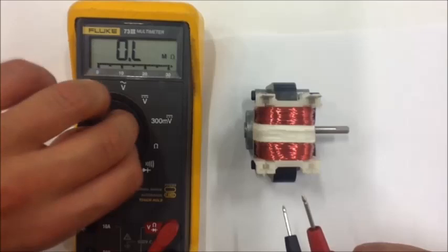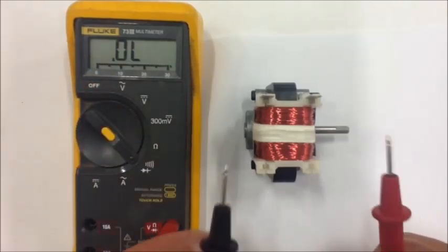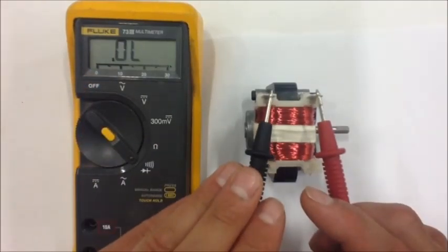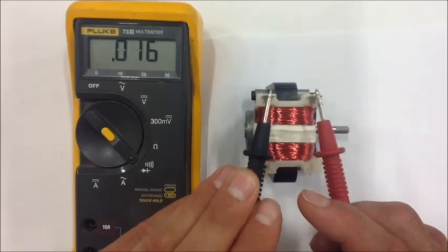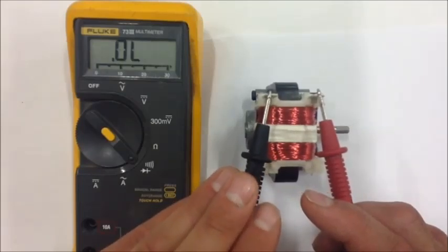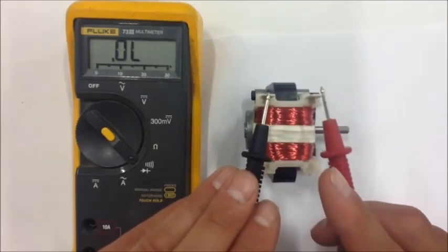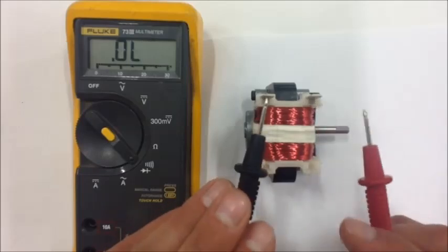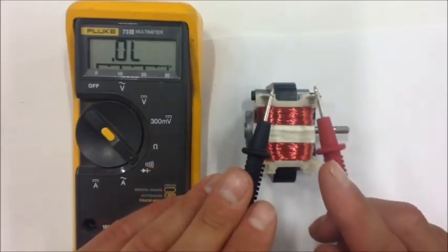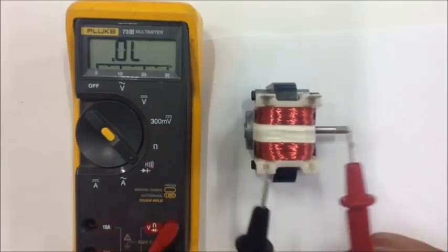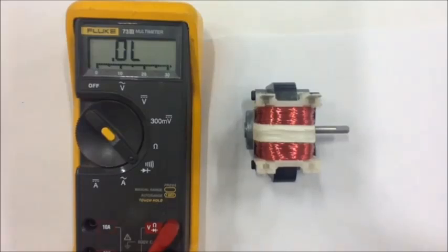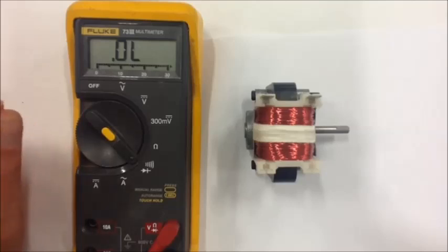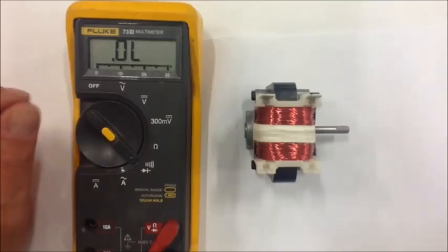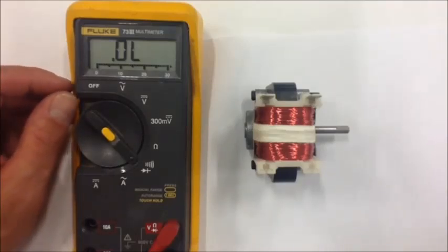So our motor is always going to have resistance, and it's also always going to have continuity on that winding. Again, if you're doing some troubleshooting and your motor isn't functioning properly, one of the first tests to do is just check to see if there's continuity. If you have continuity on all of your windings, then you can begin to compare those windings to one another and do some resistance checking, and the resistances should all match as well.